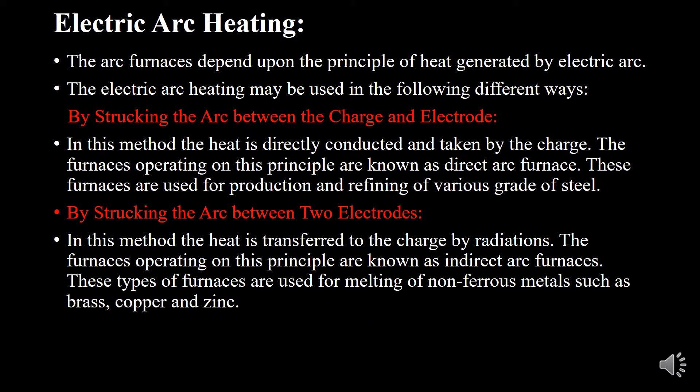While we discuss about electric arc heating, the arc furnaces depend upon the principle of heat generated by electric arc. There are mainly two ways: by striking the arc between the charge and electrode, and by striking the arc between two electrodes. In the first method, the heat is directly conducted and taken by the charge. The furnaces operating on this principle are known as direct arc furnaces, used for production and refining of various grades of steel.